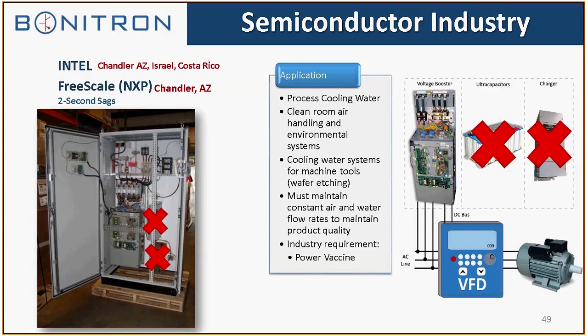Most of the time you're going to run into specifications that just cover SAGs. In this case, both Intel and Freescale required SAG ride-through. We provided a full cabinet system, single unit, backed up the motor, just to maintain constant air and water flows for product quality.